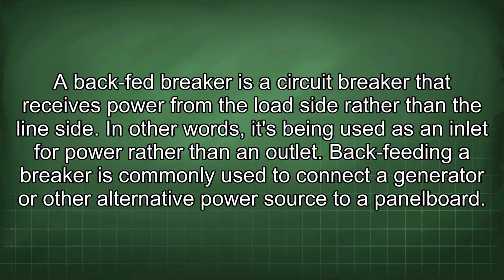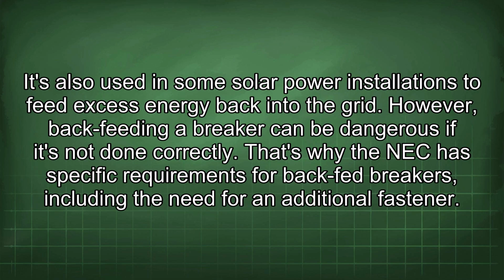A backfed breaker is a circuit breaker that receives power from the load side rather than the line side. In other words, it's being used as an inlet for power rather than an outlet. Backfeeding a breaker is commonly used to connect a generator or other alternative power source to a panel board. It's also used in some solar power installations to feed excess energy back into the grid. However, backfeeding a breaker can be dangerous if it's not done correctly. That's why the NEC has specific requirements for backfed breakers, including the need for an additional fastener.